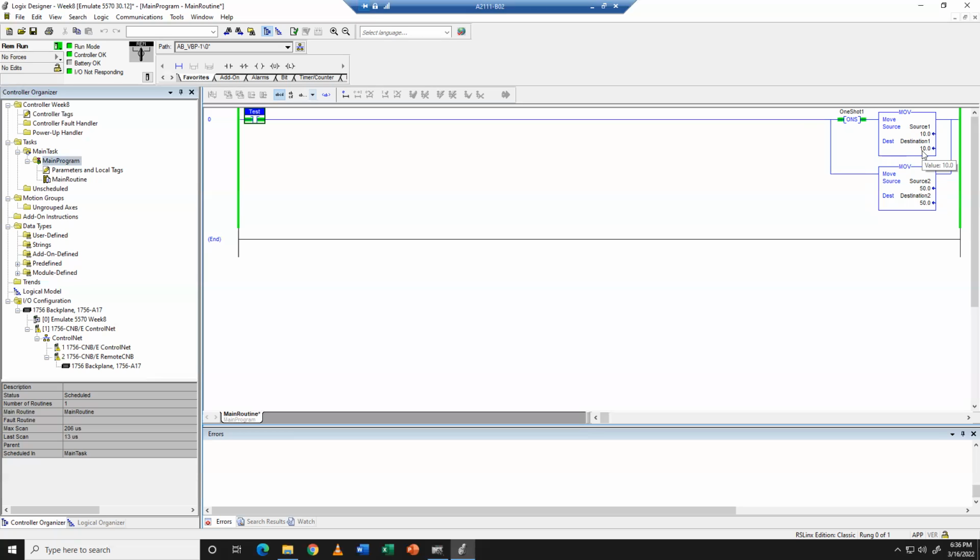So why would this be useful? Well, if we want something to only happen once, if you want to trigger a TOF timer with a one shot, so you know that something will happen and then turn on and then allow the timer to turn off a device or run without being held high. I see this a lot. We see this a lot with data manipulation. If you're trying to calculate averages, mins and maxes, and you only want to capture something when the max happens once, then you can run evaluations.